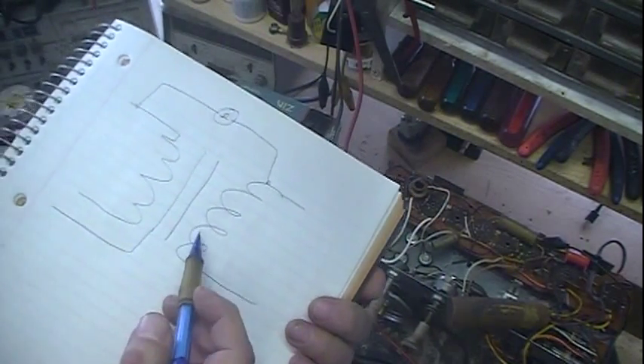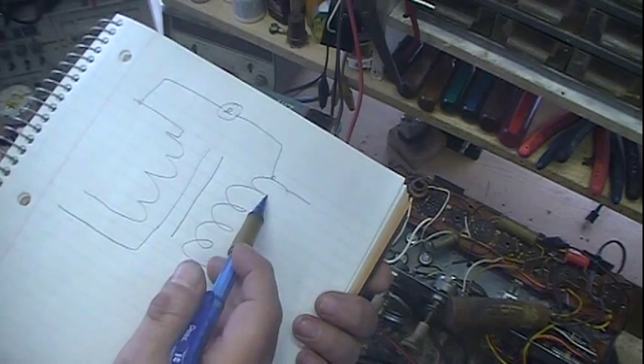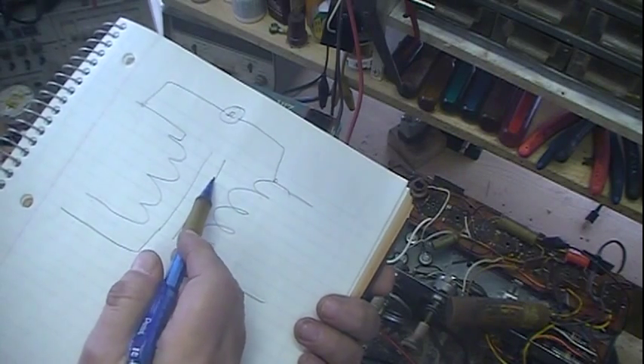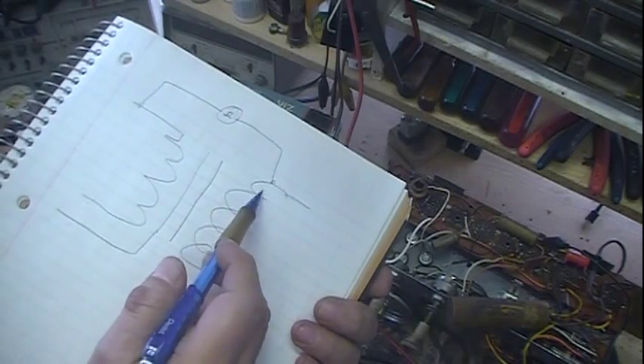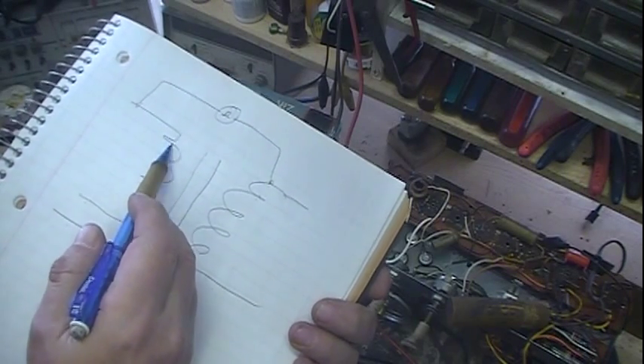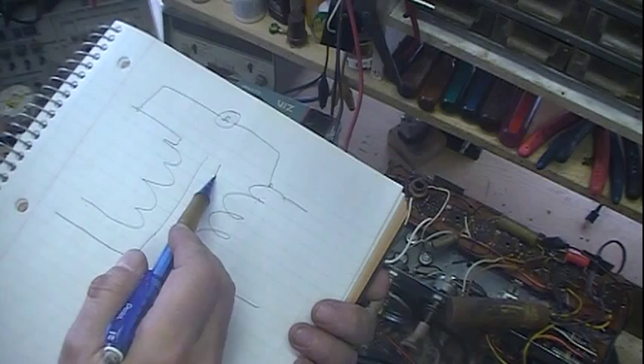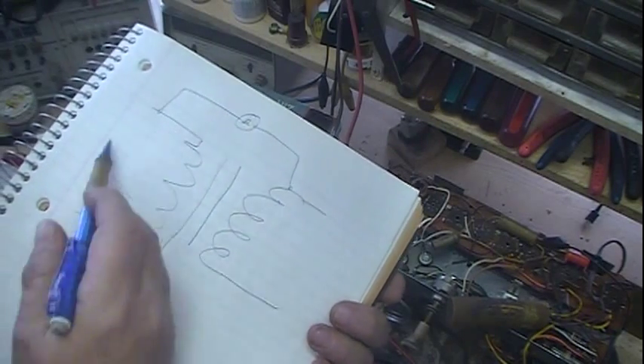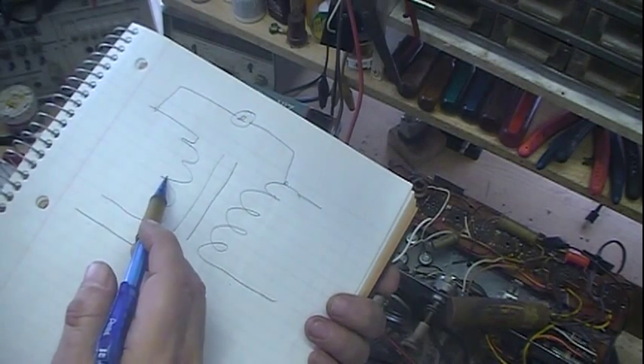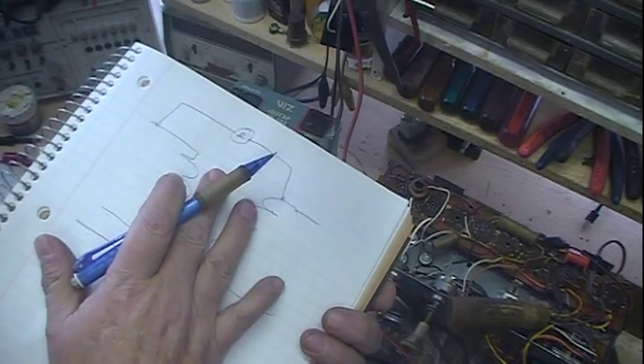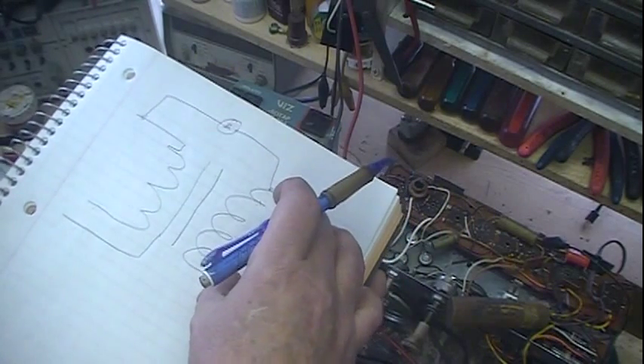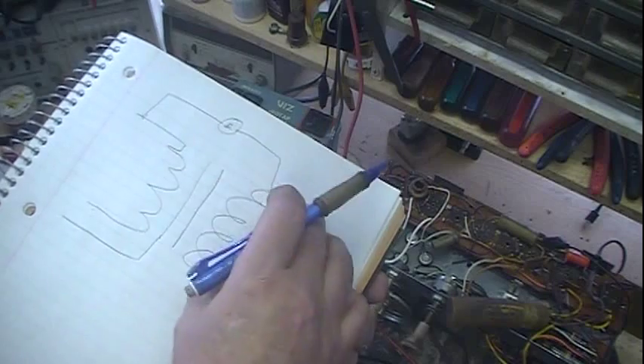And what that showed was there's no shorts - no short between this winding and the core, no short between this winding and this winding, no short between this winding and the core. So nothing is shorted, the isolation transformer is good. It is electrically isolated, there's no connection.